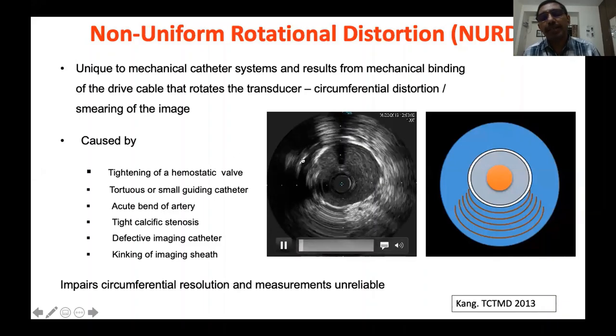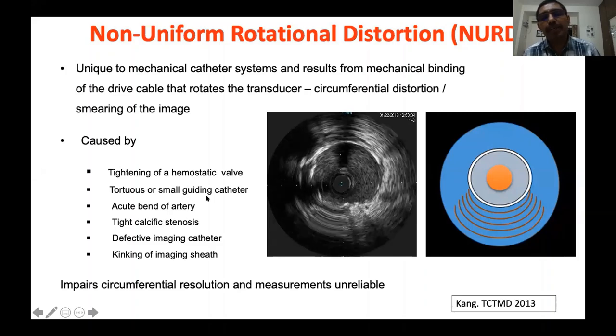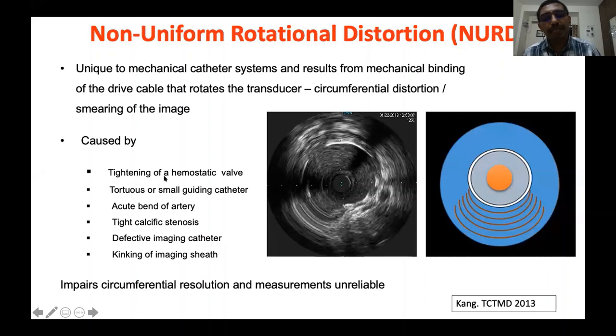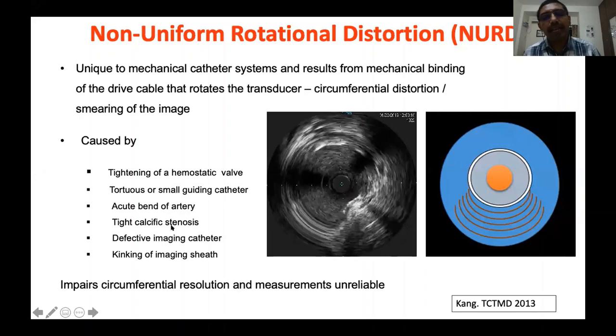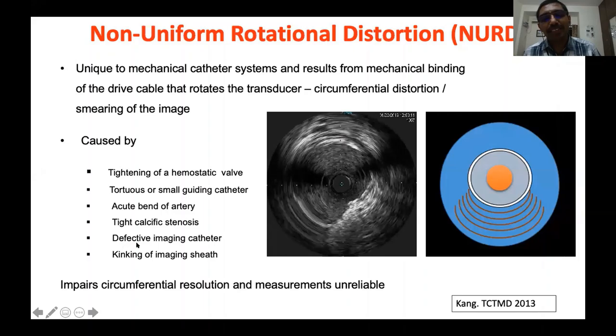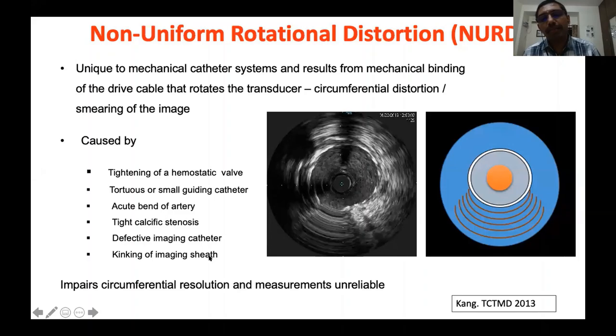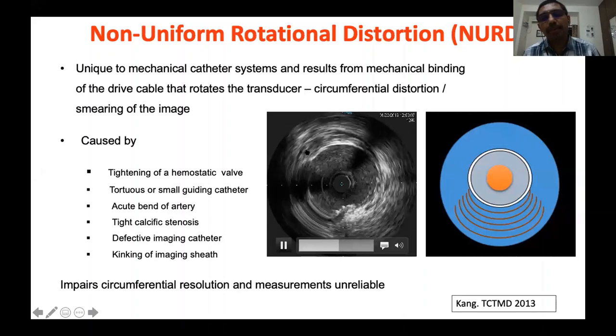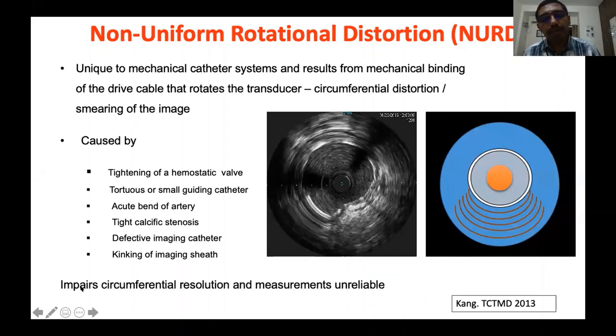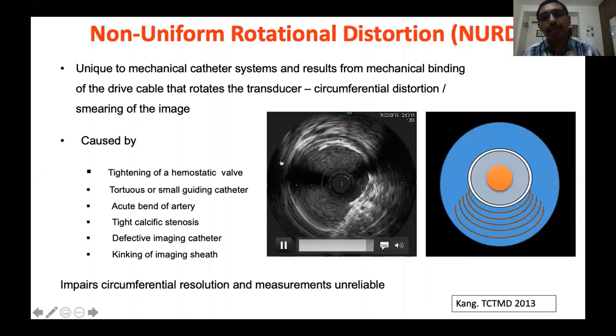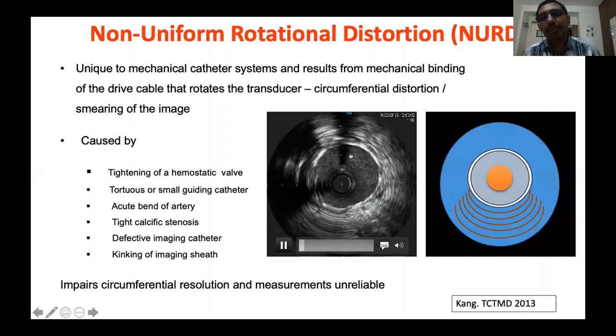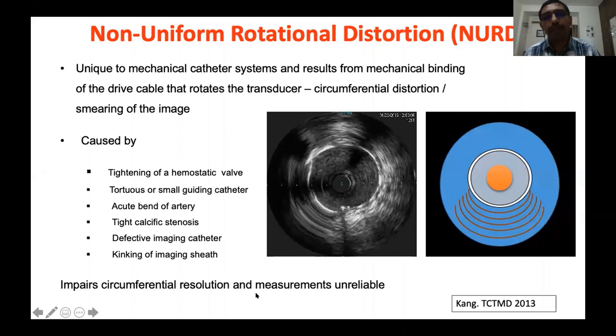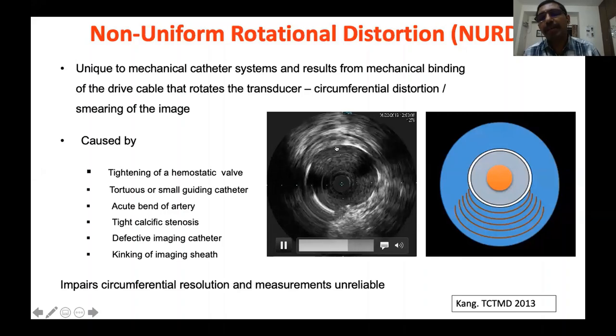NURD is caused by: tightening of the hemostatic valve if too tight, use of tortuous or small guiding catheters (5 French guiding catheter or guide catheters with multiple curves such as Amplatz catheters), acute bends in the artery, tight calcific stenosis, and most commonly in our setup — defective imaging catheter due to repeated use. These result in non-uniform rotational deformation. The clinical importance: it impairs circumferential resolution and makes measurements unreliable. It does not occur in phased array systems because they have no rotating element.